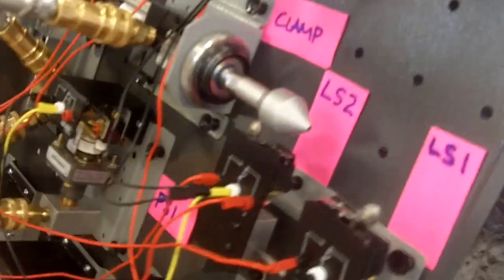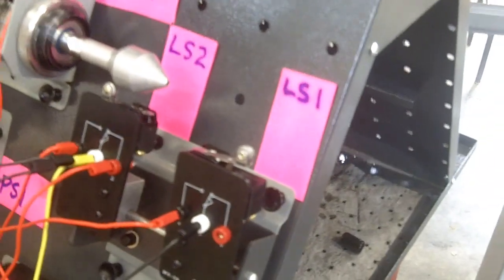The error I've introduced is I have rotated limit switch one, if you see right there, out of the path of our clamp cylinder.